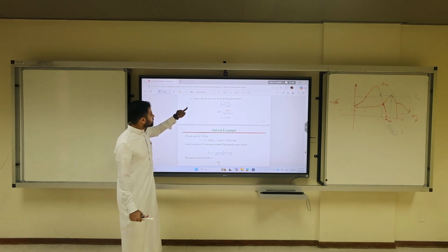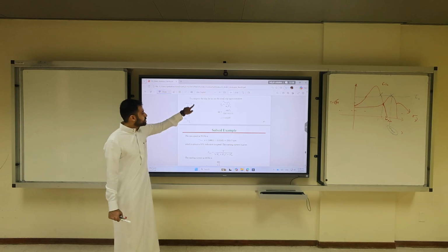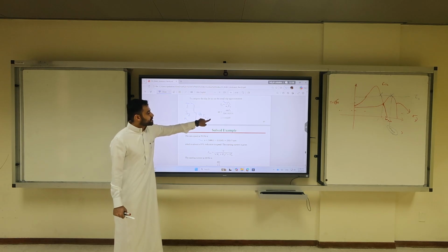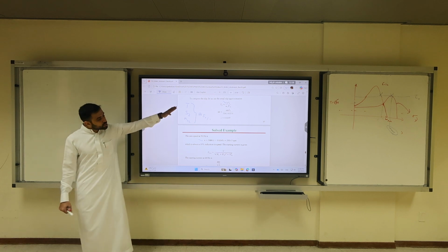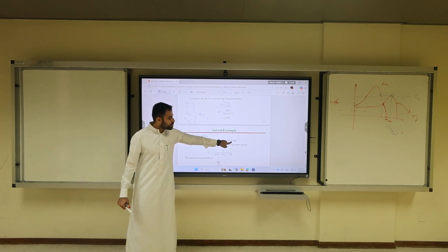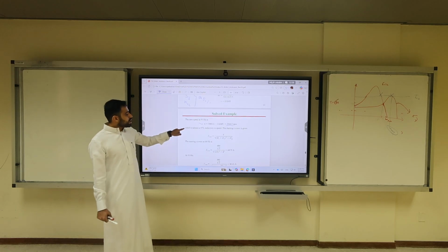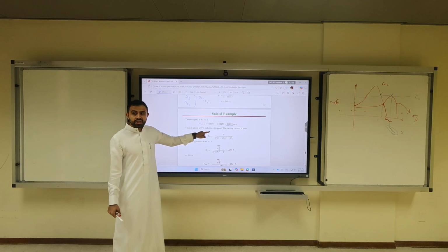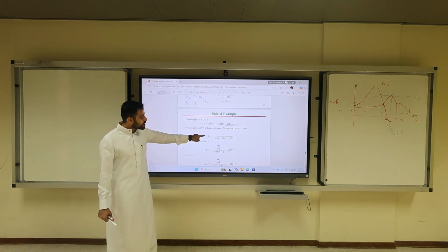So you get the slip, then you get the speed, if it's not given, through the torque. You get the torque, then you get the slip 2, and then you get NS2. 2 means the new one, at 50 Hertz. Is it clear? Yes. So you get the torque, you get the slip, you get the new speed, which is 2926.5. The synchronous speed is 3000. That's a 19% reduction in speed compared to 3500. Then you calculate the starting torque.